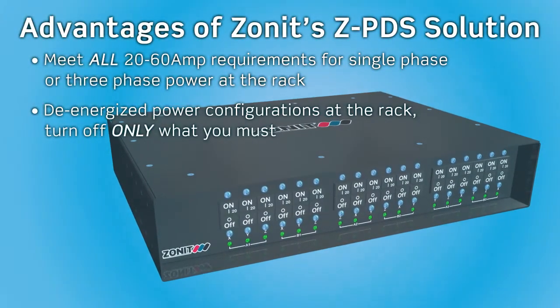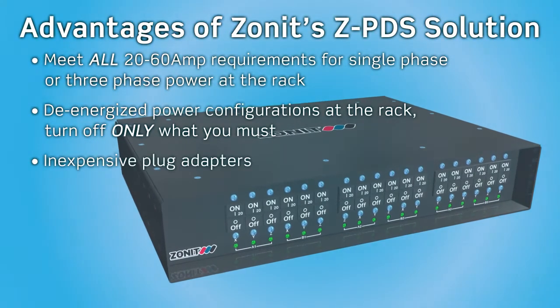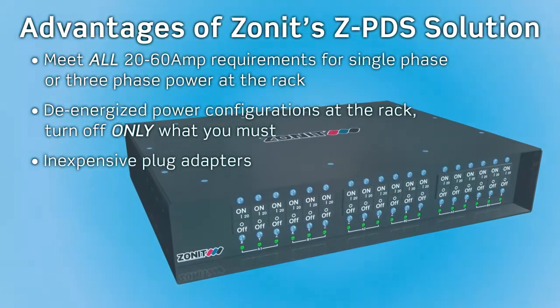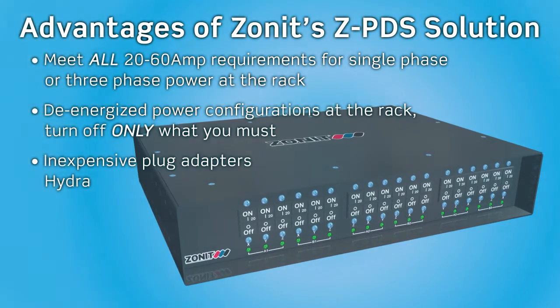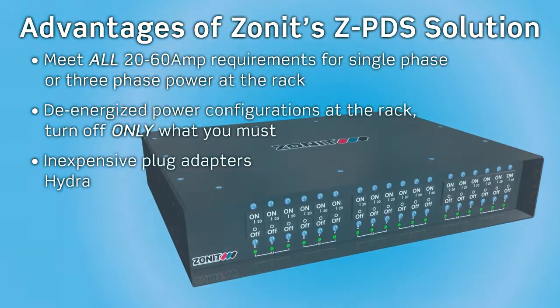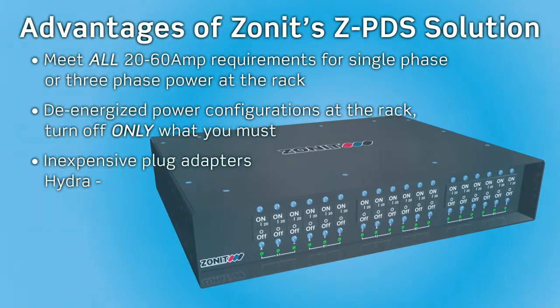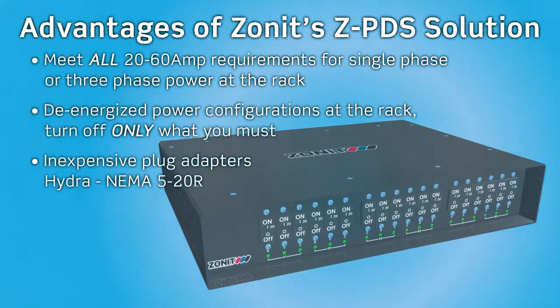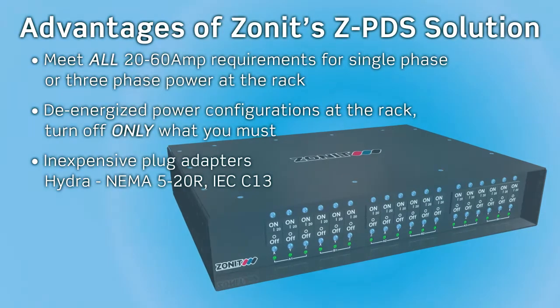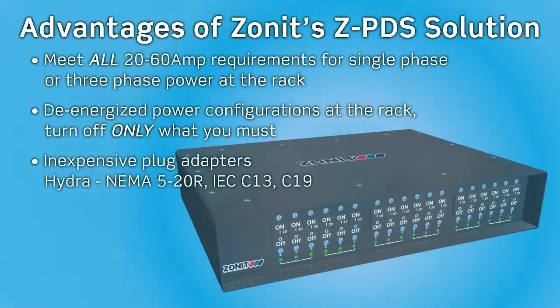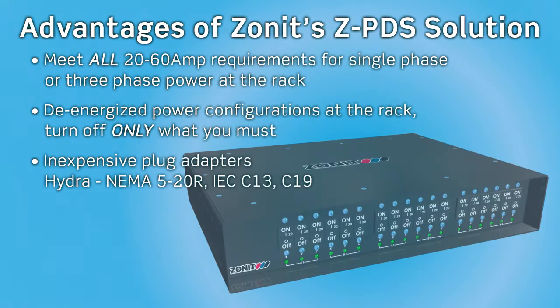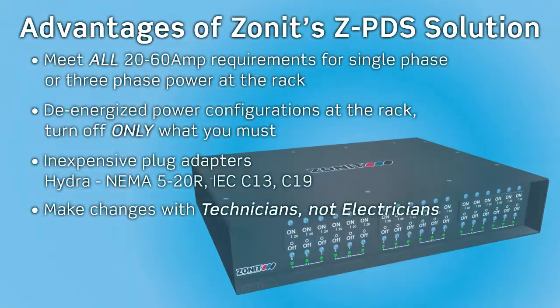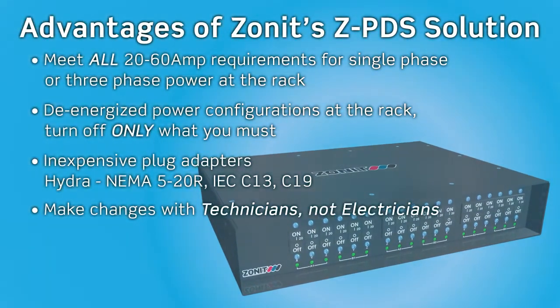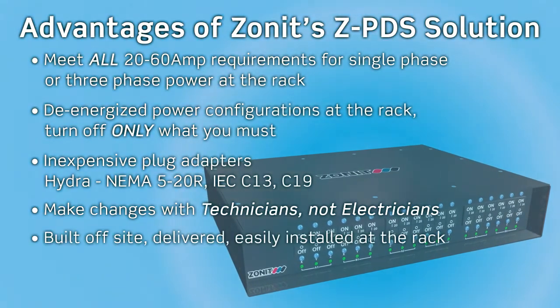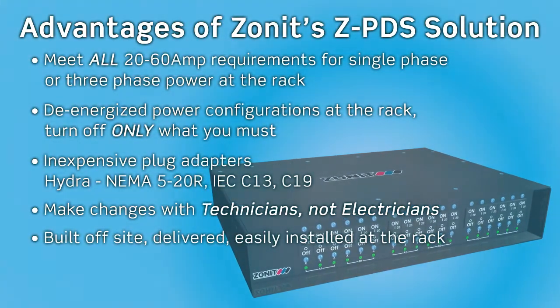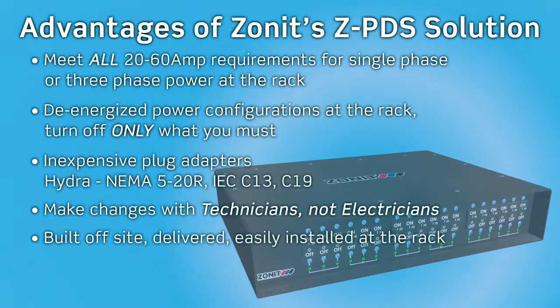Changes in output receptacle type are made via inexpensive plug adapters. This includes Hydra plug adapters that plug into the Z-PDS Unit 3-phase outlet receptacles and provide multiple single-phase outlets, including NEMA 520R and IEC C13 or C19. Data centers can make needed changes themselves using staff technicians, not electricians.